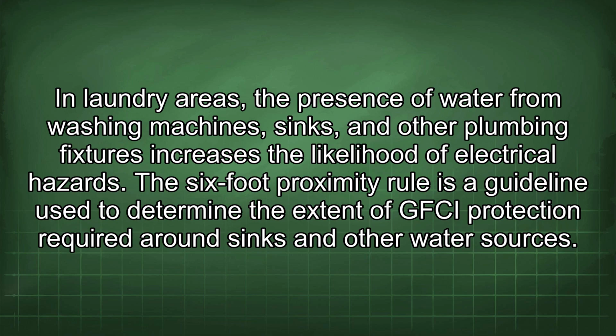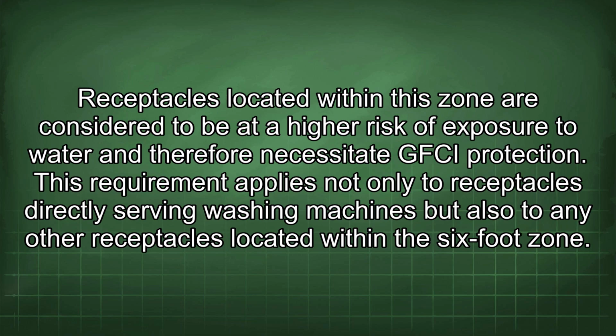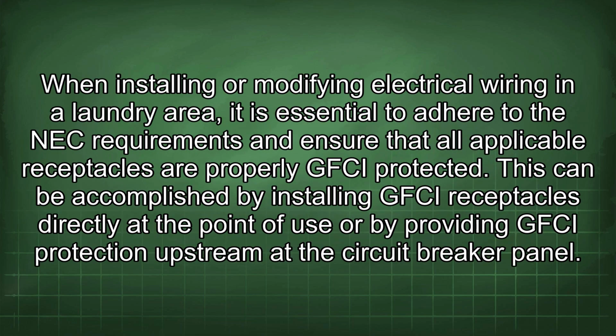The 6-foot proximity rule is a guideline used to determine the extent of GFCI protection required around sinks and other water sources. Receptacles located within this zone are considered to be at a higher risk of exposure to water and therefore necessitate GFCI protection. This requirement applies not only to receptacles directly serving washing machines but also to any other receptacles located within the 6-foot zone. When installing or modifying electrical wiring in a laundry area, it is essential to adhere to the NEC requirements and ensure that all applicable receptacles are properly GFCI protected. This can be accomplished by installing GFCI receptacles directly at the point of use or by providing GFCI protection upstream at the circuit breaker panel.